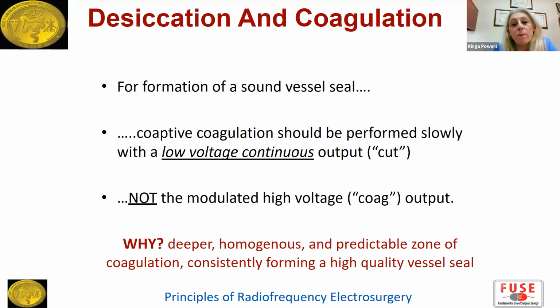Although any kind of waveform may be used for sealing a vessel, for coaptive coagulation, or when you're holding a blood vessel between your DeBakey's and want to seal it, you should perform this with a low voltage continuous output from the cut mode, the yellow button, not the high voltage coag output. People want to know why, so I'll explain: a continuous low voltage output, the cut mode, results in a more homogeneous coagulation of the vessel, with a predictable zone of coagulation.